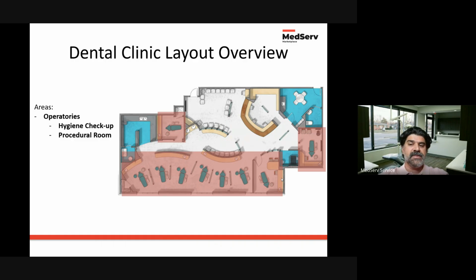Typical pieces of equipment in the operatory include the dental chair itself, the delivery unit, which has the handpieces and the different tools they use during the procedures, and the lights, which are similar to surgical lights. There are suction lines with vacuum units that are used to evacuate different materials from the cleaning processes. There are interfaces for controls, switches, pedals, as well as displays. And these are all connected to a centralized infrastructure somewhere else in the clinic. So operatories are the endpoints of the utility system. They don't typically generate the problems in those areas, but they expose where the problems can be coming from.